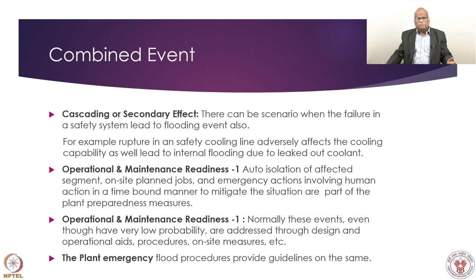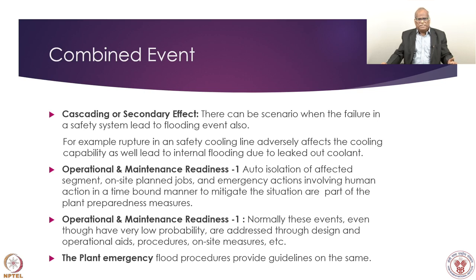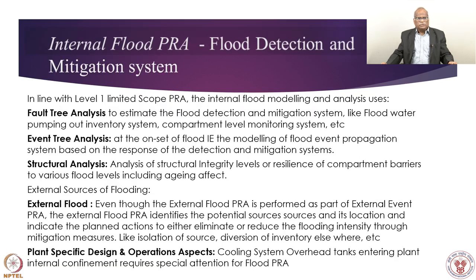This requires readiness at the operations and maintenance level — different segment isolation, various activities, availability of systems, and what mitigating measures are available. For safety systems we do periodic testing; for flood mitigation systems also, periodic testing must be done. We consider low-probability and high-probability events. All plants have flood procedures, and their adequacy and effectiveness have to be checked and validated. Plant emergency flood measures and the guidelines available for handling them must be reviewed.